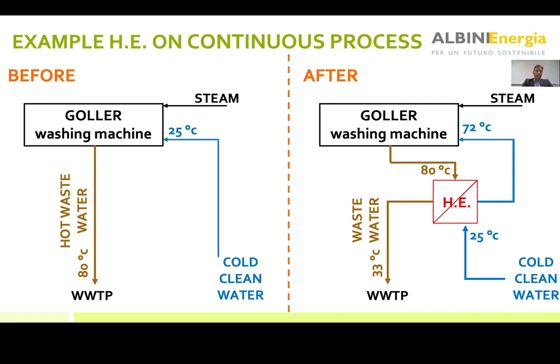The machine was discharging at 80 degrees and the cold clean water entering the heat exchanger was at 25 degrees. In order to reach the temperature required by the recipe, they used to rely on normal steam. After the heat exchanger installation, the washing machine discharge was still 80 degrees, but by using the heat exchanger, this temperature dropped to 33 degrees before going to wastewater treatment, and the fresh water was raised from 25 degrees to 72 degrees.